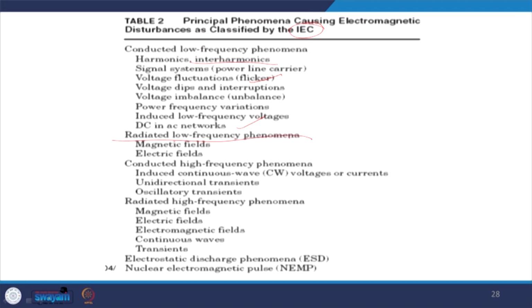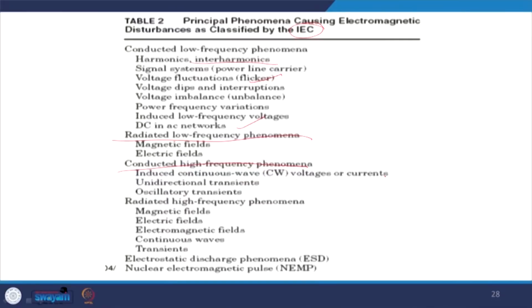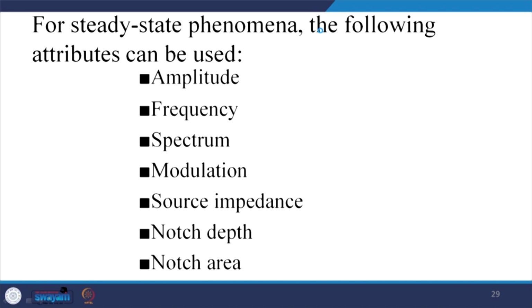Thereafter radiated low frequency phenomena: magnetic field, electric field, with EMI-EMC noise. Conducted high frequency phenomena: induced continuous wave, CW, voltages and currents, unidirectional transients, oscillatory transients. Radiated high frequency phenomena are due to the magnetic, electric and electromagnetic fields, as well as continuous waves and transients. Then electrostatic discharge phenomena, that is ESD, mostly used for the electrostatic precipitator, and the nuclear electromagnetic pulse, that is NEMP. So these are the few principal phenomena causing electromagnetic disturbance, and for this you have a special standard, that is IEC. Otherwise, this is for the conducted emitted noise, and we may talk later about the problem of EMI-EMC. Power quality is also a part of EMI-EMC, but we generally talk more about THD and other issues here.